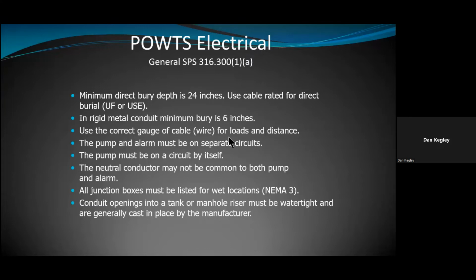Using the correct gauge of cable wiring for loads and distances. Obviously, your fractional horsepower pumps are only going to need either 14-2 gauge wire or 12-2 wire. However, if you're going longer distances, you do need to compensate for voltage drop. The code does talk about 3% and 5%. Basically, for a branch circuit, going from your circuit breaker to feed your pump, it wants a maximum of no more than 3% voltage drop between that circuit breaker and the pump. And then it can be up to 5% for the total load of the circuit, like a feeder going to a sub panel, going to the device at the very far end.